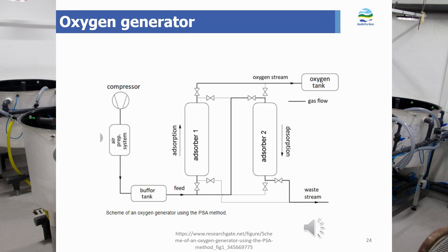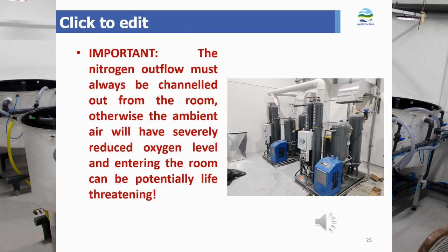It is recommended to keep oxygen purity at least above 92%, otherwise quality will be highly compromised. It is very important that nitrogen exhaust must always be channeled out of the room, otherwise the ambient oxygen level will be severely reduced and entering the room can be potentially life-threatening.